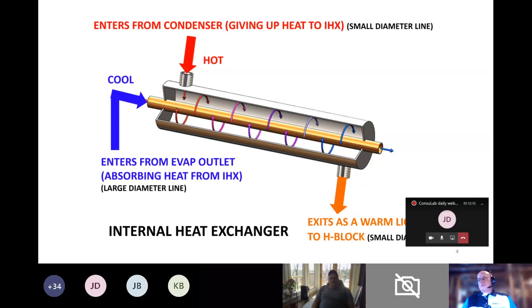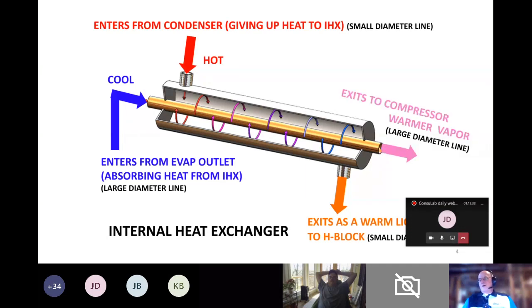The one larger low side line coming from the evaporator outlet connects to the IHX, where the refrigerant vapor is heated by the heat taken from the high side line. They are not internally connected, but only transfer of heat occurs. This heat ensures that any liquid droplets are boiled off so that we don't slug the compressor. It leaves the IHX on the large line and heads off to the compressor.